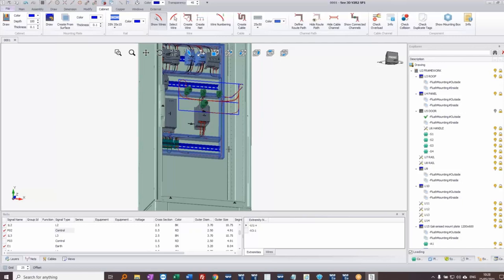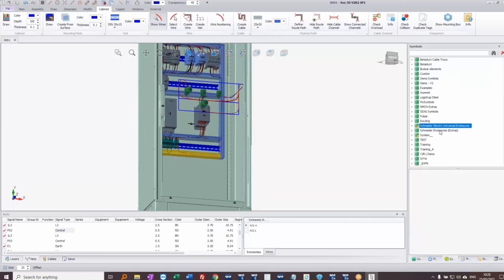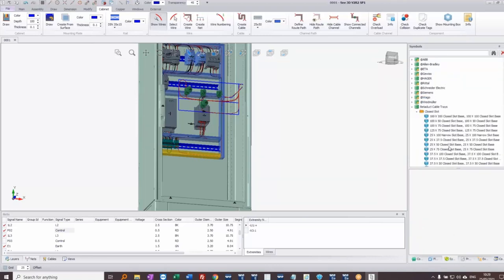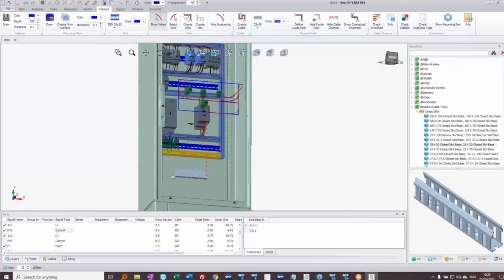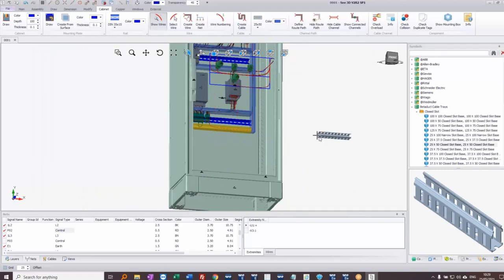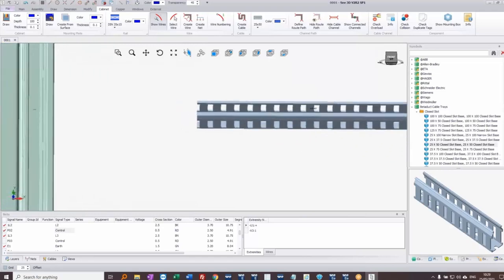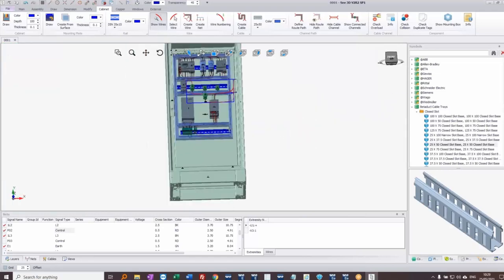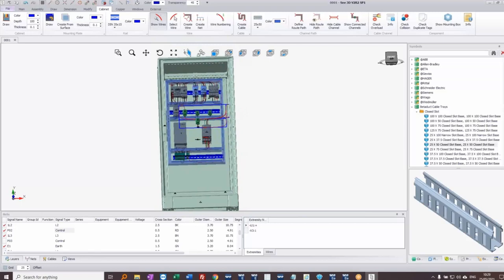I could put cable ways on the back of the door as well. I've only used basic wireways here — I could have used ones from a manufacturer like Betaduct, selecting a closed slot 25 by 50 from the symbols library, and stretching it to whatever size I need. These symbols are parametric so they snap into the right position. Fancier routing elements are available, but I've kept it simple for this demonstration.